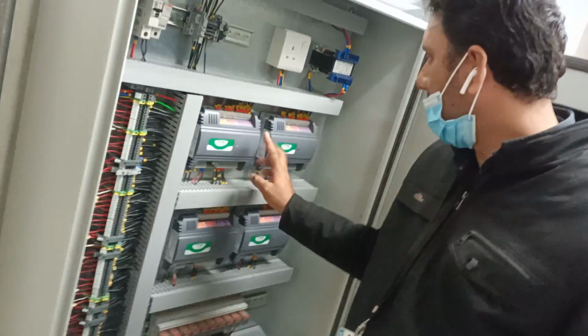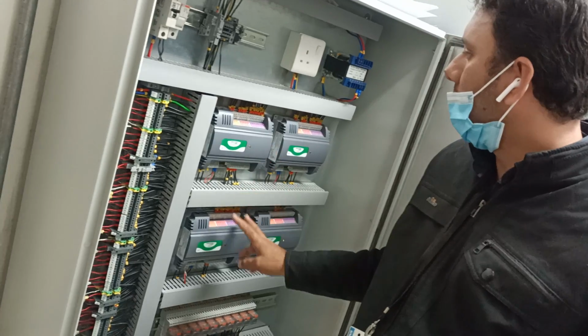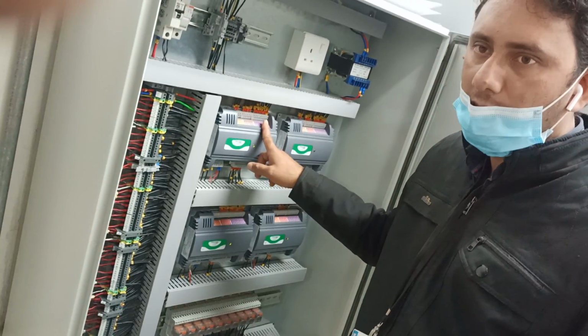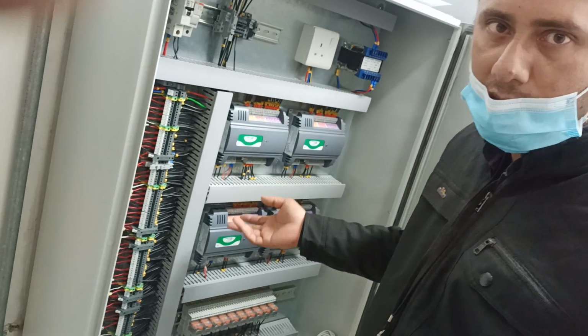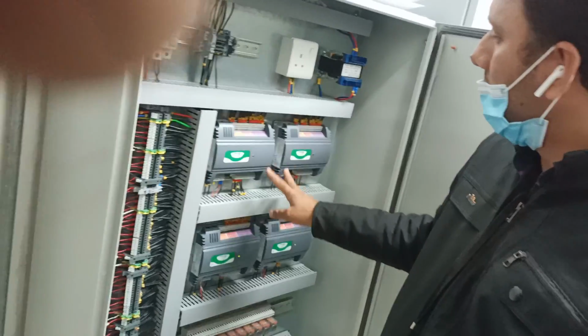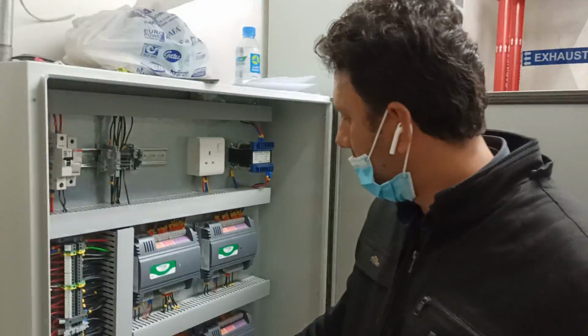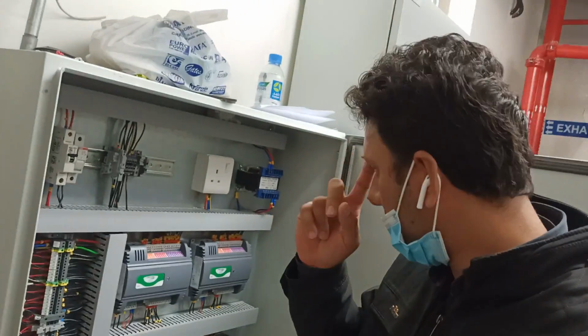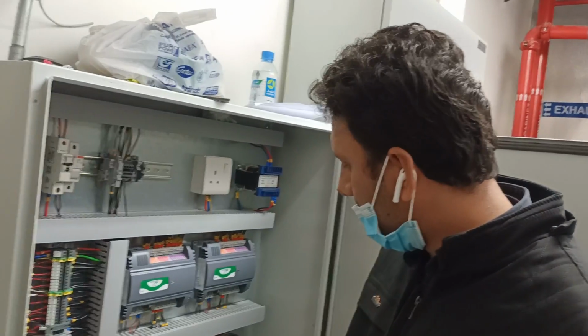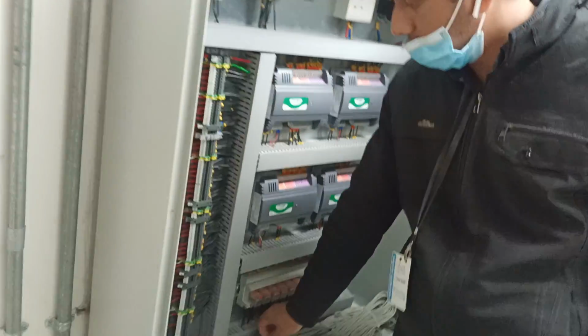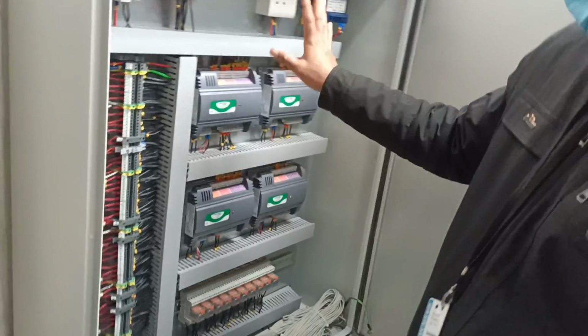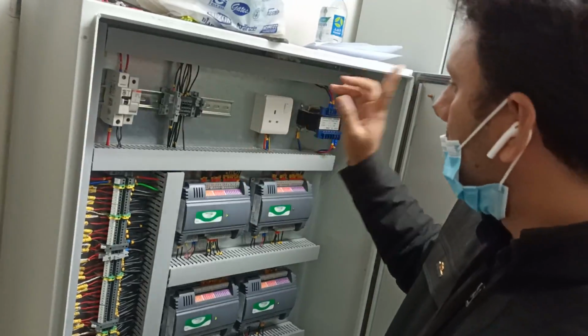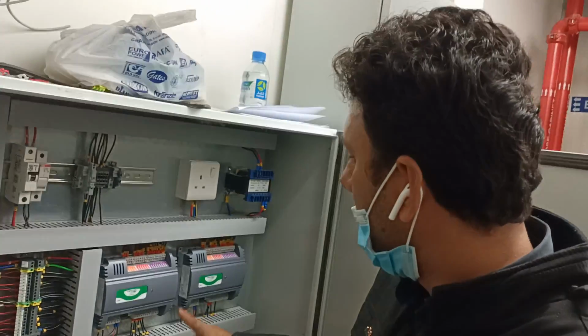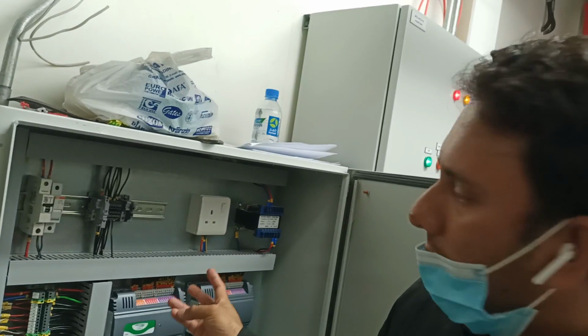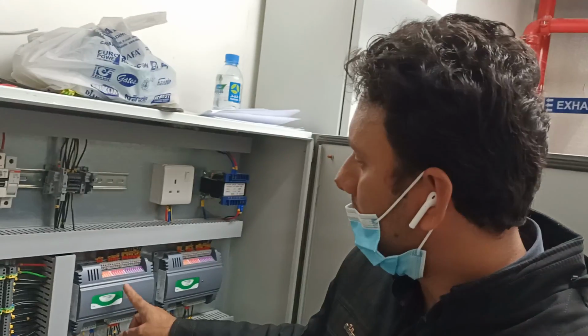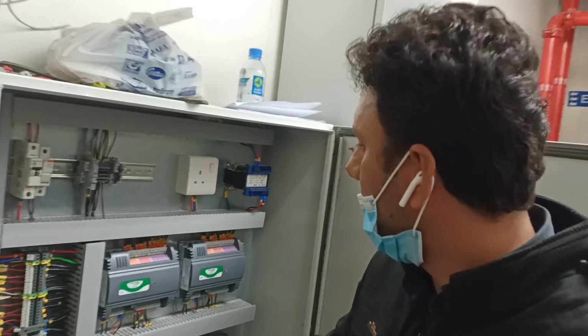So here you will see there are 4 controllers. Why do we need 4 controllers? Because each has very few ports, and we needed more than 20 or 30. Because of that, according to the terminals required, we use 4 controllers. This controller is connected with the BMS network, and for the BMS network we have used the same BMS cable. This can be operated through the BMS system, and the operation of the supply fan, return fan, VFD, all these things are already indicated with this BMS.